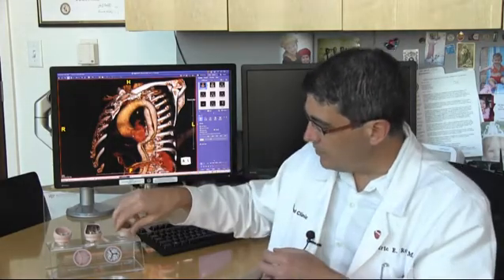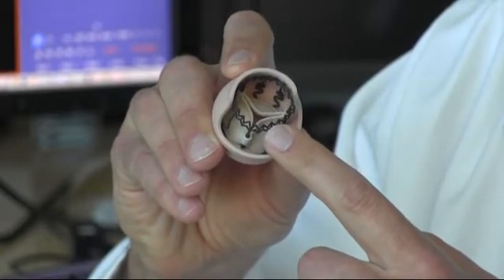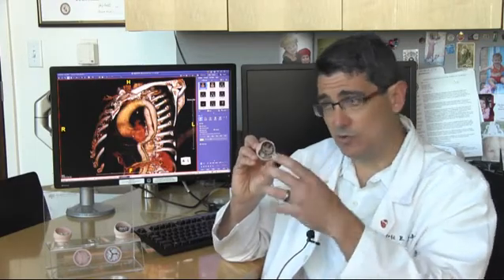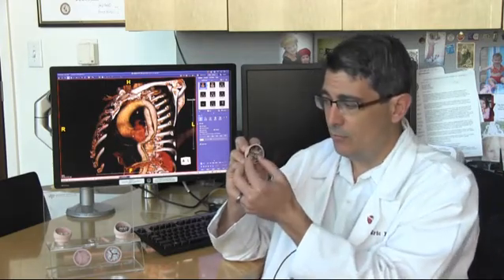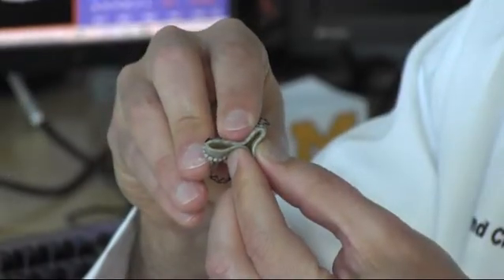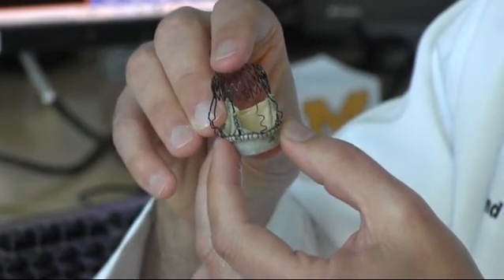We now also have a new technology — a hybrid between those two approaches — and that is a sutureless valve. This model demonstrates the now commercially available Perceval valve. We still address the native diseased valve through a surgical approach and cut it out, but instead of placing 12 to 20 sutures inside the aorta, this Perceval self-expanding valve — of which I have an actual sample here — is delivered inside the aorta, and when released, the stent seals and holds it in place with no sutures at all.